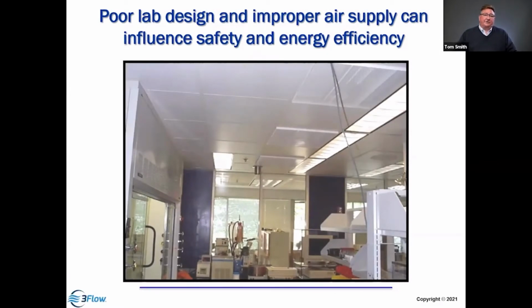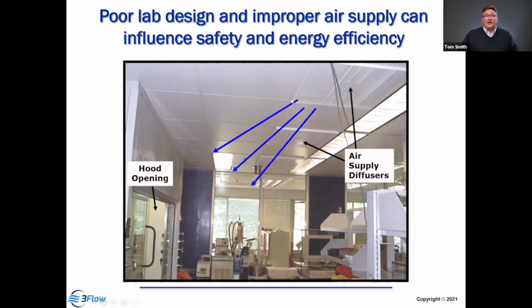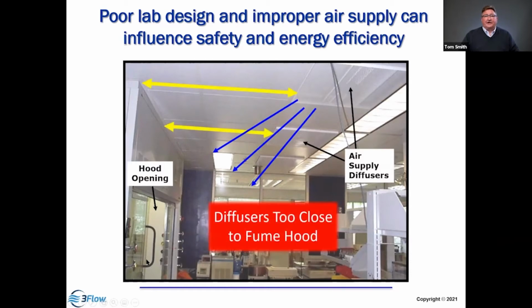Another factor that we're going to look at is the supply. So we have our hood here, our supply diffusers in the ceiling. Now you may look at that and say, well, that looks okay. But what if we looked at the distance of the diffusers from the opening and said that cross drafts are really important? If the ceiling tiles are 2 feet by 2 feet, then we know that this diffuser is 1 foot, 2 feet away, so 3 feet to the diffuser. And when we look at the airflow patterns of discharge, they are blowing right at this opening, and that diffuser is too close.